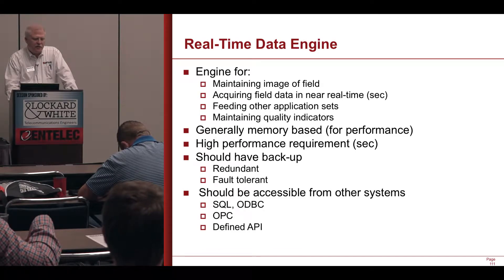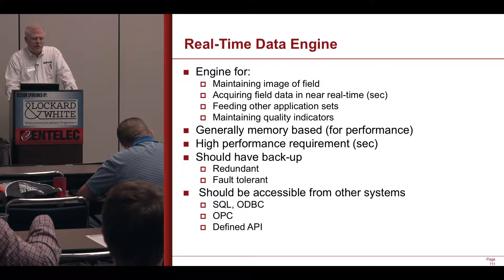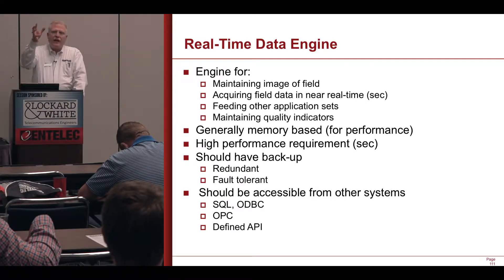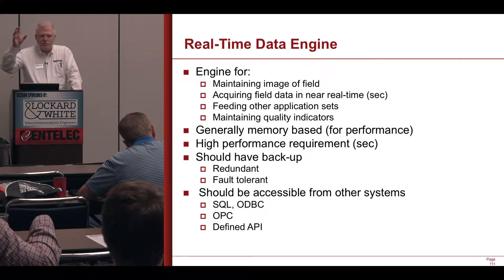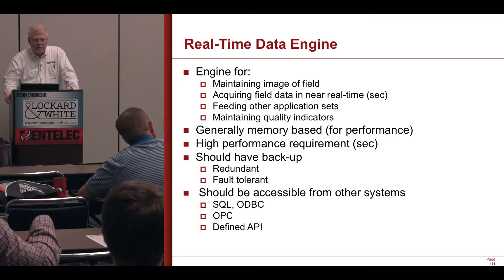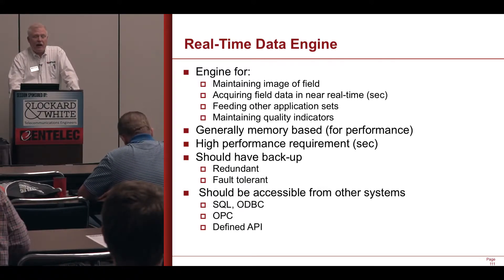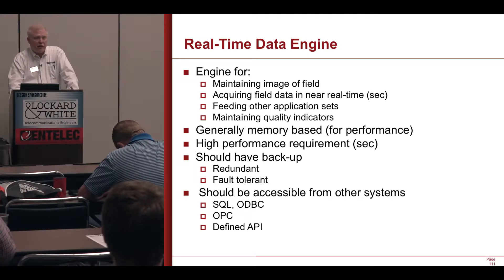The real-time data engine is where I've got an image of the real-time data, and it's where I'll feed other applications that need to see real-time data. Generally in the real-time database, they run that application in RAM on the server, so it's fast. It needs to be high performance. Ideally you're going to be able to back it up without taking it offline, and it should support redundancy as well.